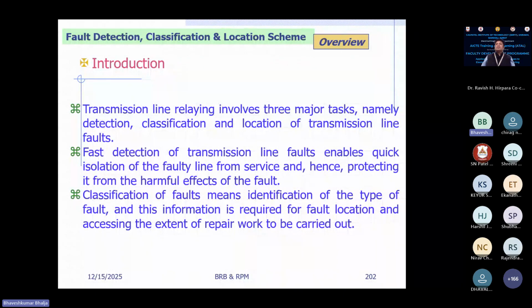So what is the requirement for a transmission line? The requirement is that you detect the fault very fast. You have to isolate it using the circuit breaker, which is SF6 or maybe some other type; vacuum is not used beyond 33 kV or at most 6 kV. Now they are using some hybrid type of circuit breaker, which combines SF6 with some other gas, right?